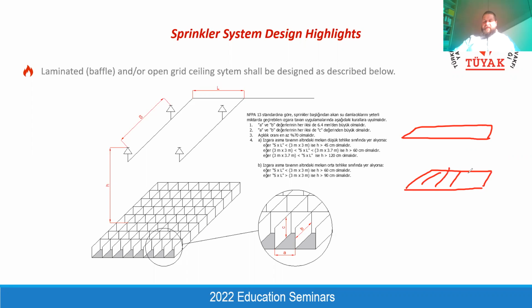We have three different rules. First of all, the openness of this ceiling should be more than 70%. The first rule is that you need to select the material of your suspended ceiling accordingly. Otherwise, you will have a sprinkler on the ceiling, on the roof ceiling level, and also you need to provide the sprinkler beneath the suspended ceiling as well.